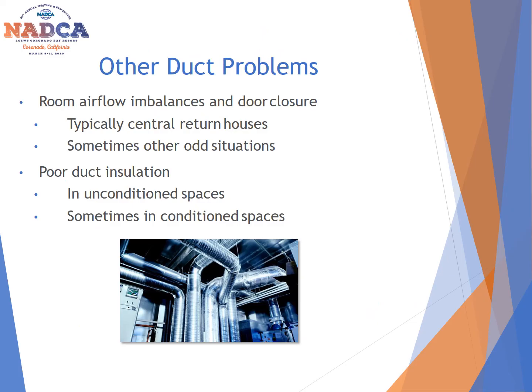There are other problems you can run into associated with airflow and imbalances. And the big one is when you have a central return in a home or in a business and you have door closures. When they did not take the fact that doors are being closed into account when they designed the system, that air now does not flow the way it should. And that creates a big imbalance within the entire HVAC system.